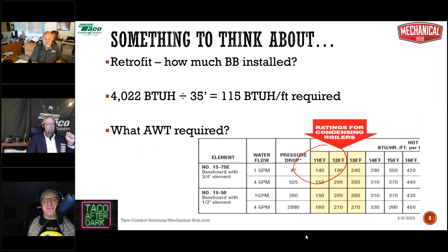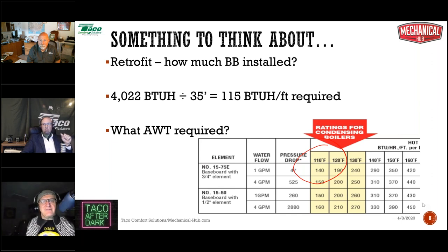When you're looking at a retrofit or a boiler replacement, how many of you, and chime in on the comment section, if you would, please, do a heat loss calculation for every boiler replacement that you do? How many of you do that? How many of you, when you replace a boiler, the first thing you do is a heat loss? Or do you simply choose the new boiler based on the size of the one you're taking out? All right, most people do that.